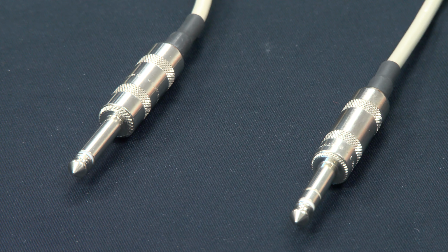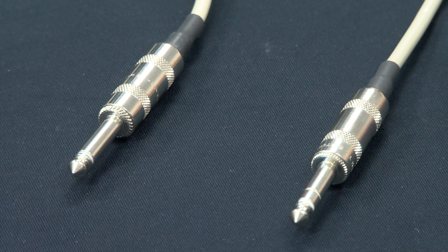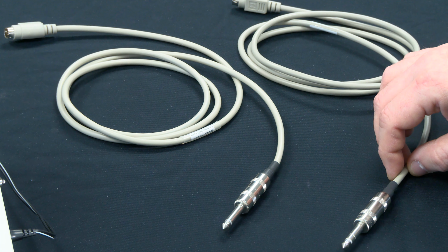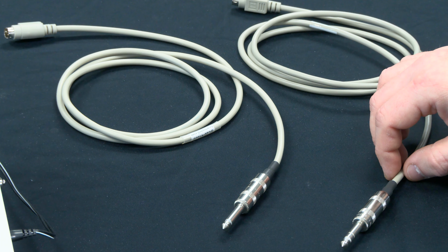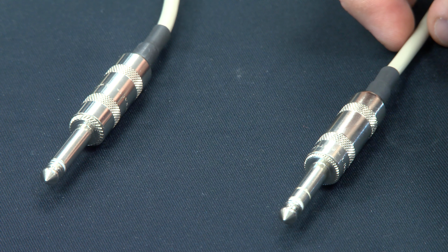BC Group does manufacture two different temperature simulation cables. One is the BC20-41333 for simulating YSI 400 series temperature probes. This cable has only two connectors at the end. The other cable is BC20-41334 for simulating YSI 700 series temperature probes. This cable is identified by the three connectors at the end of the probe. It's important when testing a monitor that you have the correct YSI cable for the monitor being tested.